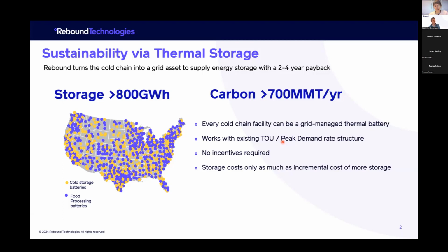This is a fantastic question. Oftentimes people assume that we stumbled into low temperature refrigeration, but we really intentionally targeted low temperature refrigeration instead of HVAC loads. The issue with HVAC loads is really on the go-to-market side. When you look at the HVAC industry, you have a couple problems. One, there's no consolidated service for HVAC systems, so you have a lot of trouble with maintenance of your equipment. On the flip side, in the cold chain, almost all facilities already have on-site maintenance staff that are already trained to work on our systems.